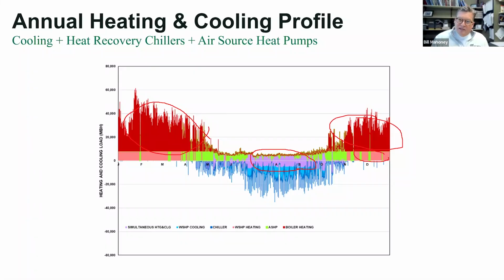It's got to be this hour of this day. I've got this much heating load, therefore I can get that much simultaneous cooling load also, but I can't do any more. Otherwise, I've got to have somewhere else to put the heat, in the ground for instance, for the light blue cooling system. That makes a lot of sense.